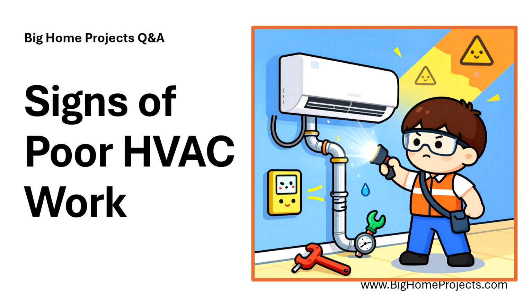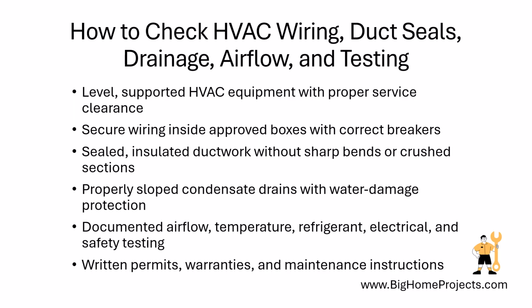How can I identify poor HVAC workmanship? You can spot it through unsafe wiring, incorrect installation, weak airflow, poor drainage, and work that fails to follow local codes or the equipment manufacturer's instructions. Start by checking whether the heating, ventilation, and air conditioning equipment sits level, is firmly supported, and has enough space for service and safe airflow.